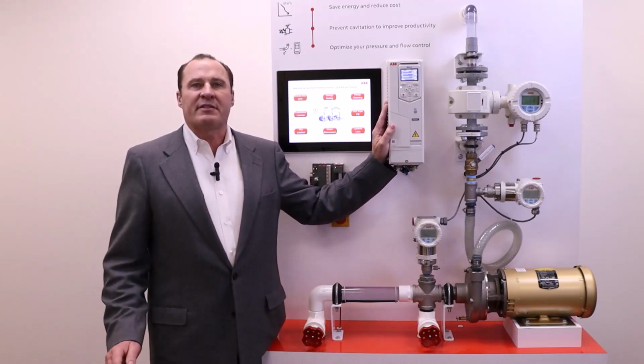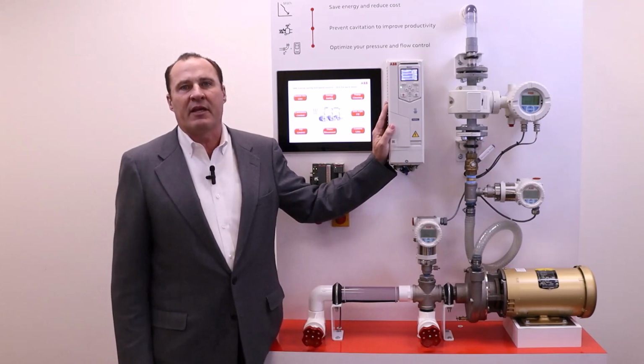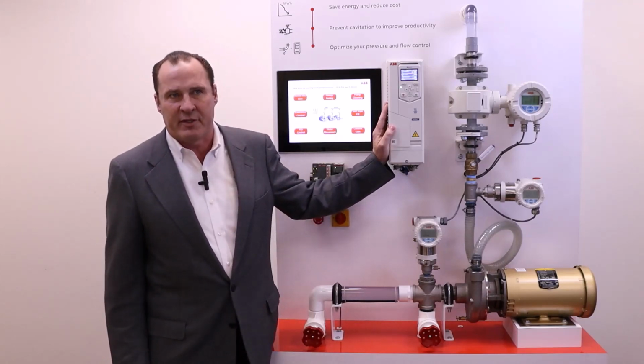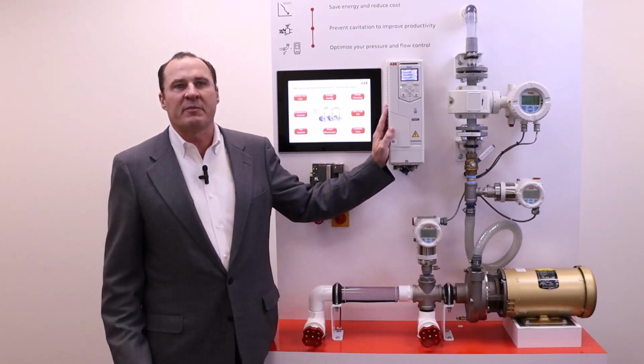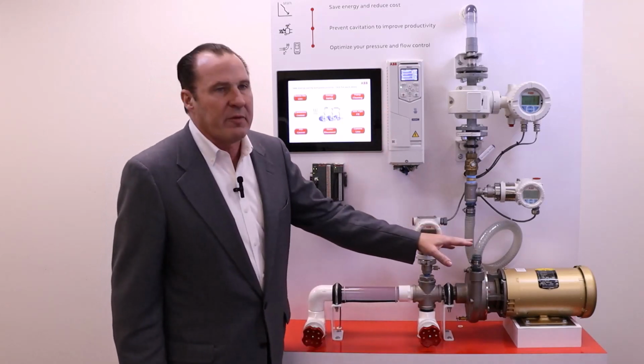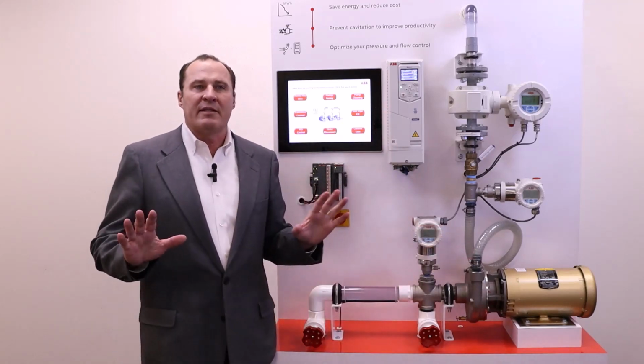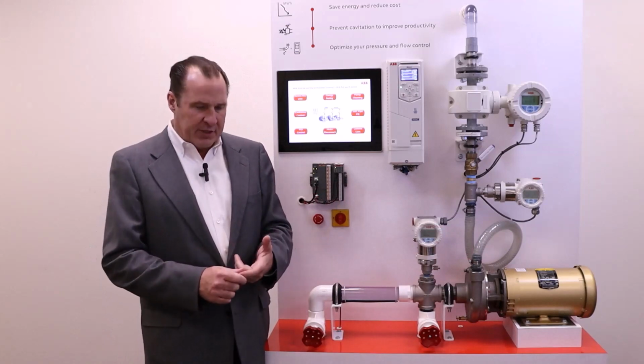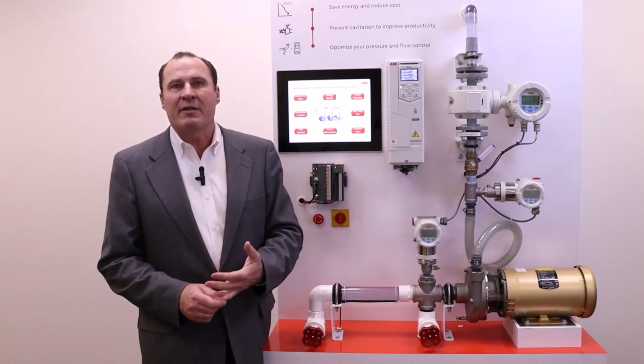Sensorless pump control is standard on the ACH580 and the ACQ580 drives family. Sensorless pump control is simple to set up for individual motor pump combinations. Only 10 data points relating head pressure to flow to power are needed.